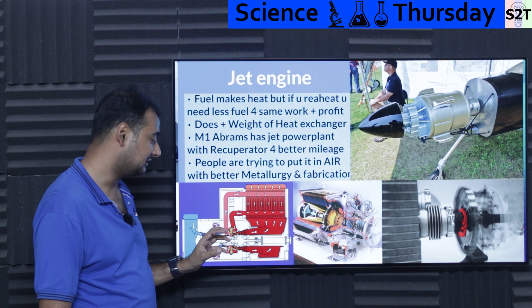The hot exhaust is very hot, as much as 600 degrees Celsius. At that point, it goes into the recuperator, which marries two things: the high pressure but lower temperature compressed air circulating to be fed to the combustion chamber, versus the exhaust trying to dump its heat. So your exhaust goes from 600 degrees Celsius down to 300, and your intake air goes from 150 degrees Celsius up to almost 250.